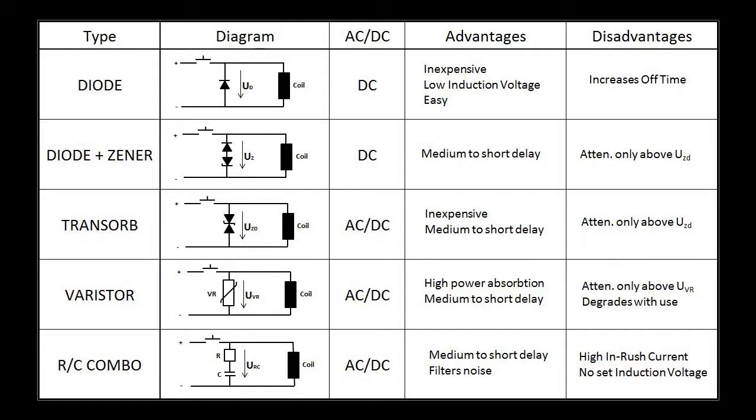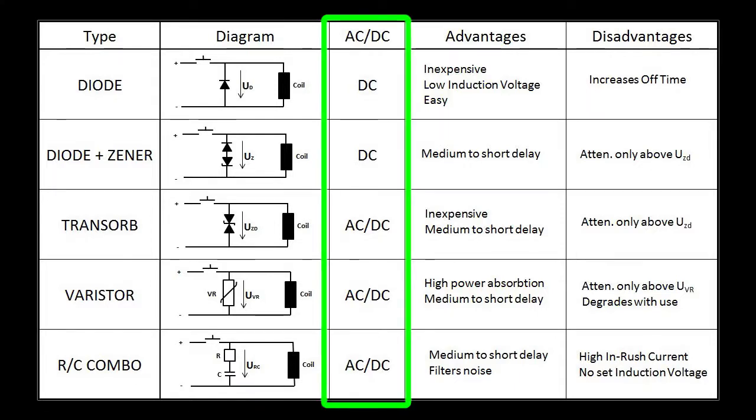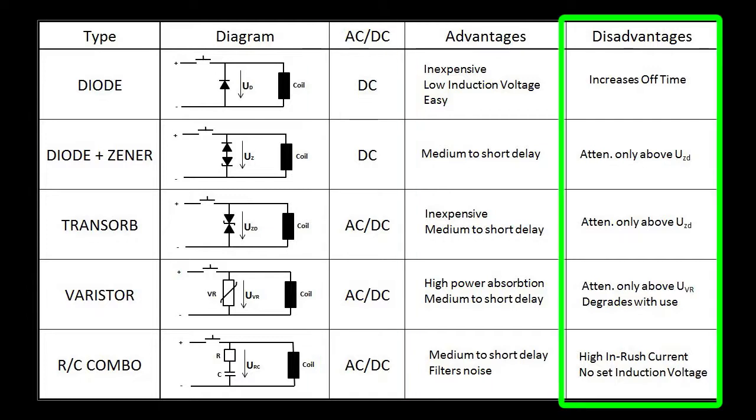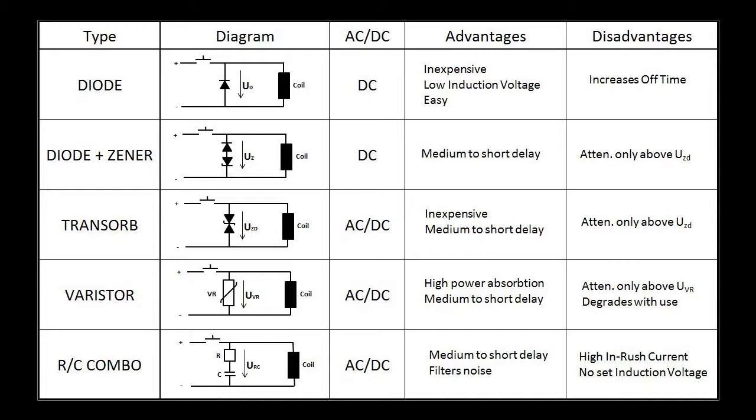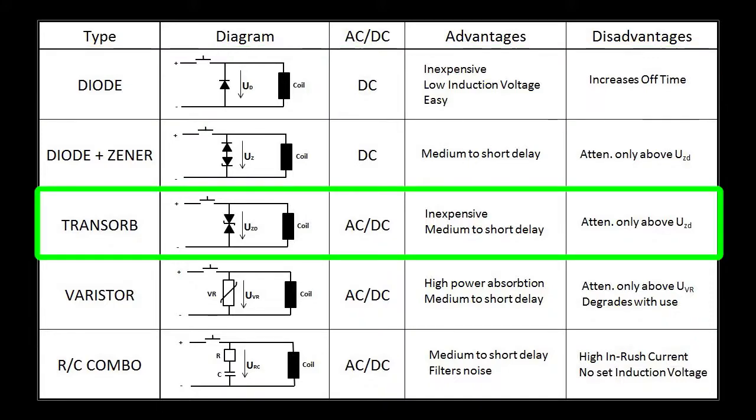This table shows you at a glance the various kinds of SPDs available, if they work for AC or DC coils and some of the advantages and disadvantages of each. In general, you'll find that for DC coils, your best bet is going to be a simple diode type surge suppressor. For AC coils, your best bet is usually going to be a transorb.